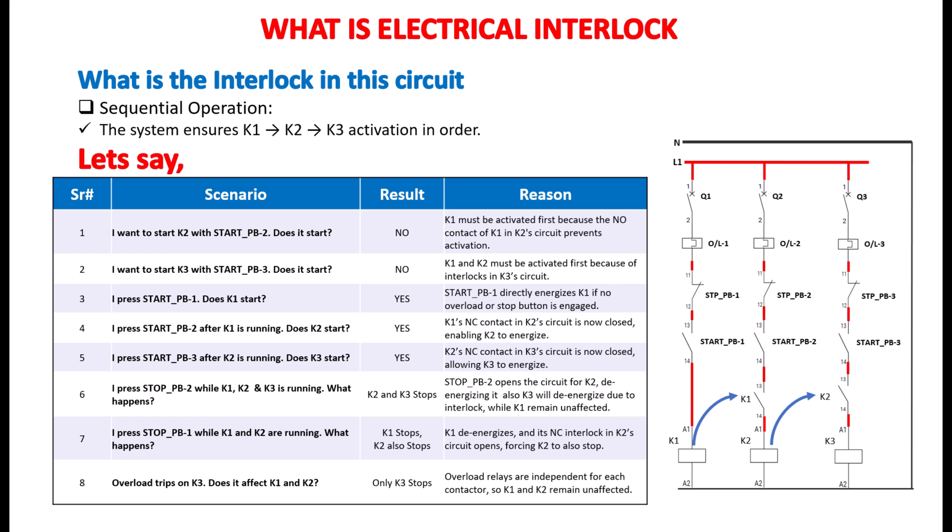Scenario 2. If I want to start K3 by pressing START PB3, will it start? Again, no, it's not. That's because both K1 and K2 must already be running. Interlocks in K3's circuit make sure it won't activate out of sequence.